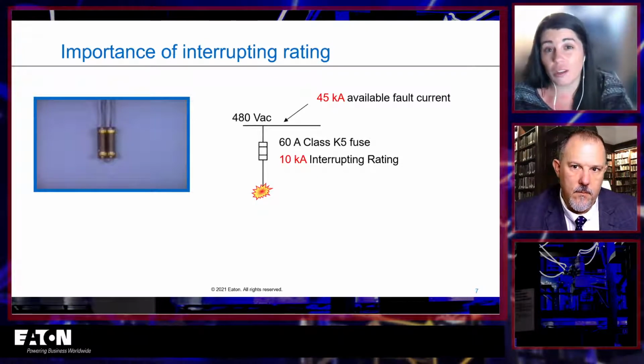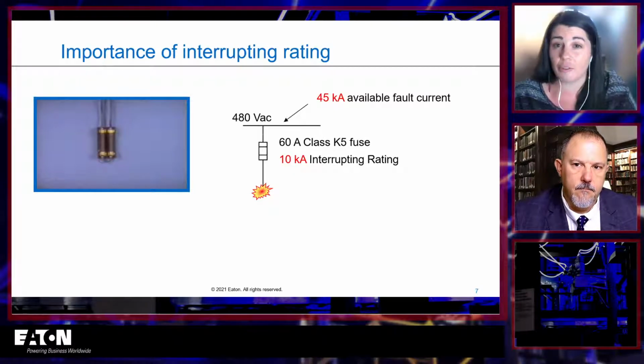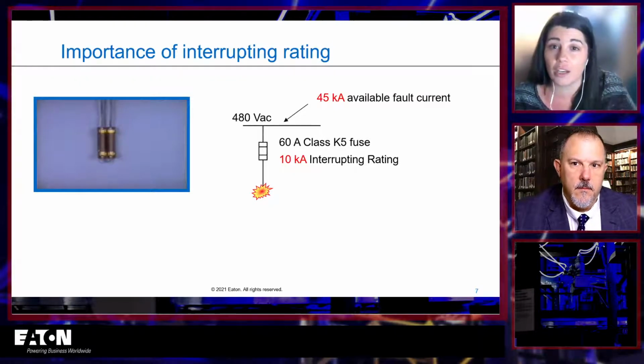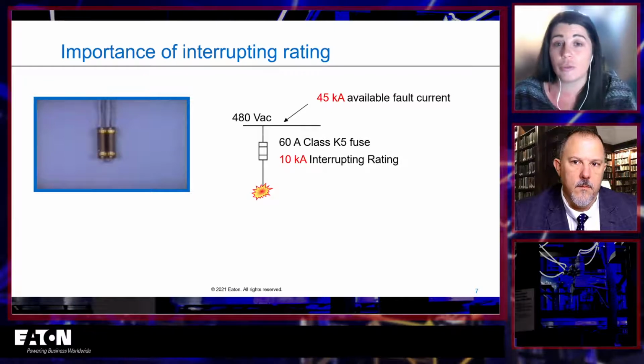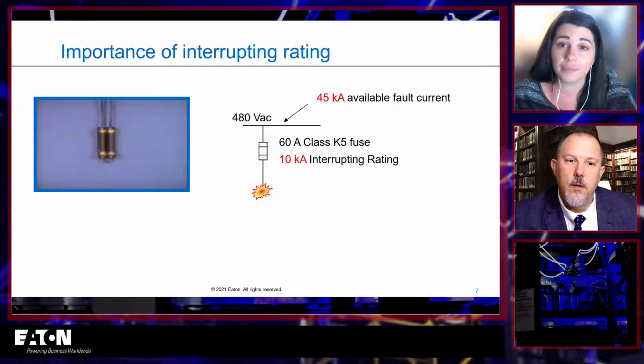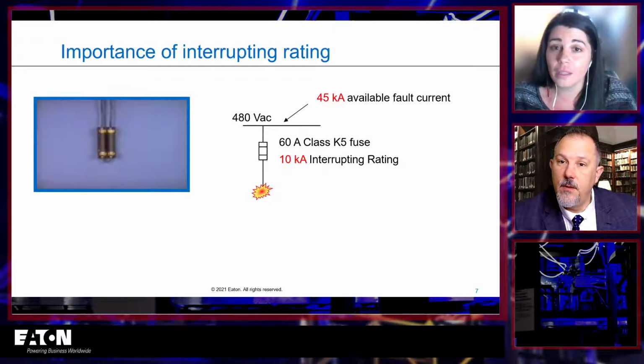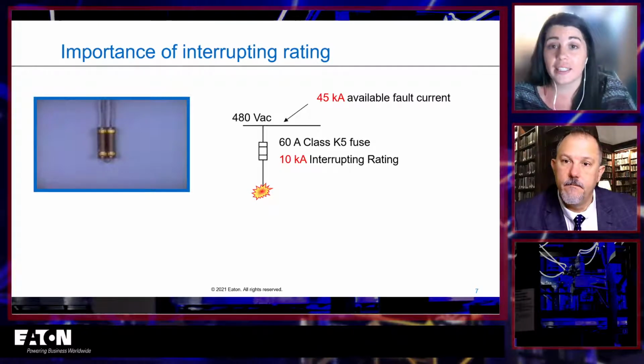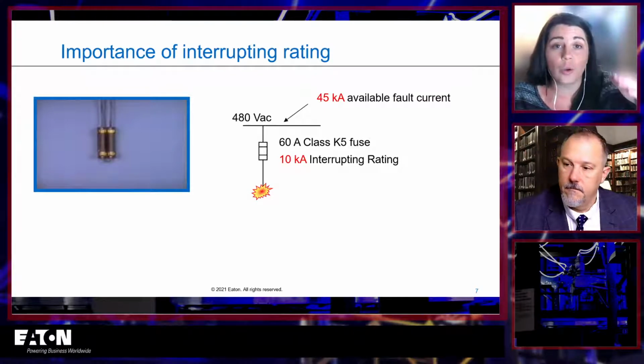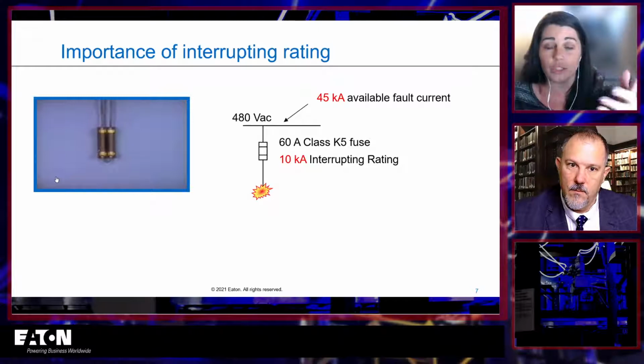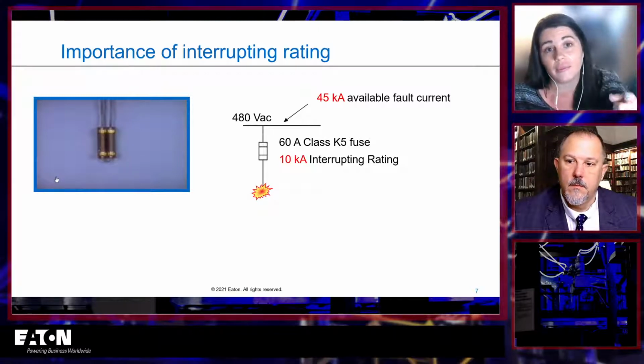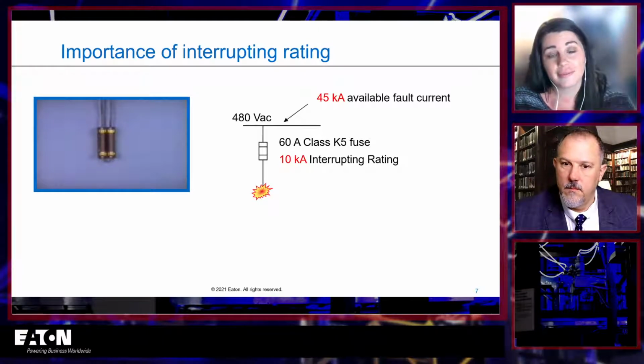So this is a much older style fuse that only has a 10 kA interrupting rating, not that high interrupting rating we typically associate with fuses. Would this be like the non-current-limiting fuse now? Yeah, similar to that, exactly. Okay. So 480, we did the same thing. We shorted across the load side. Go ahead and play the video.